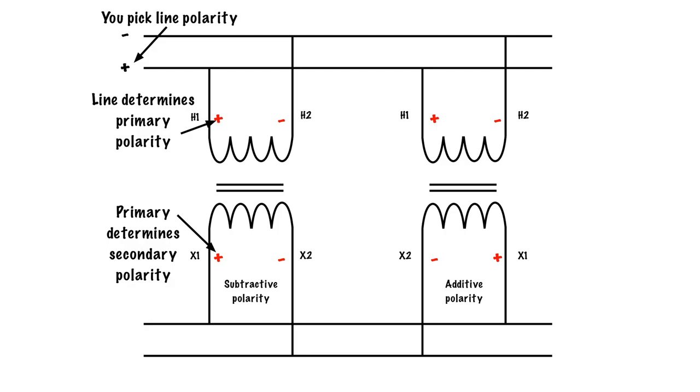So here we go. Remember that with the rule of transformers, H1 and X1 are always going to be the same polarity. So here we've got H1 is positive, so X1 is going to be positive, which means that if H2 is negative, X2 is negative.